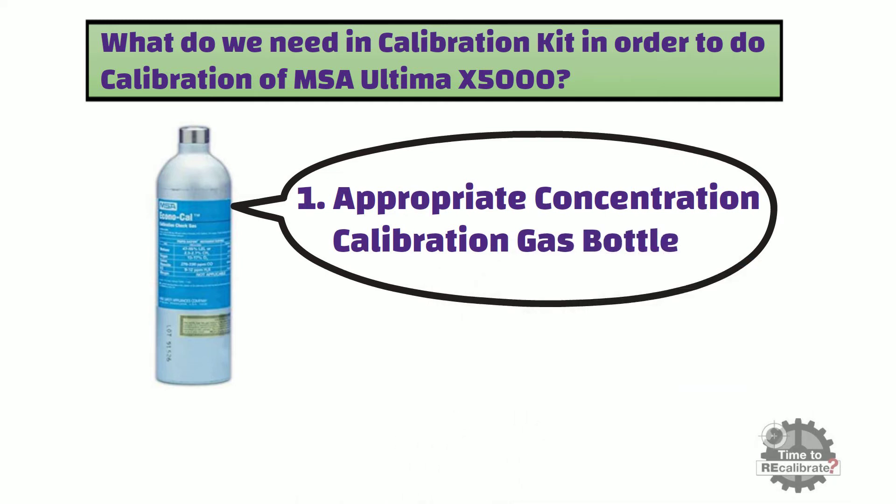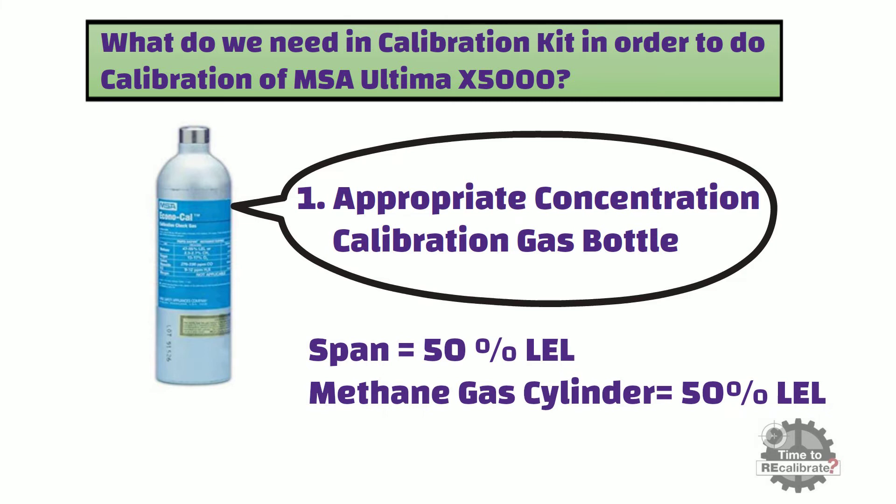For example, if device span is set for 50% lower explosion limit, we need to use 50% lower explosion limit of methane gas bottle.